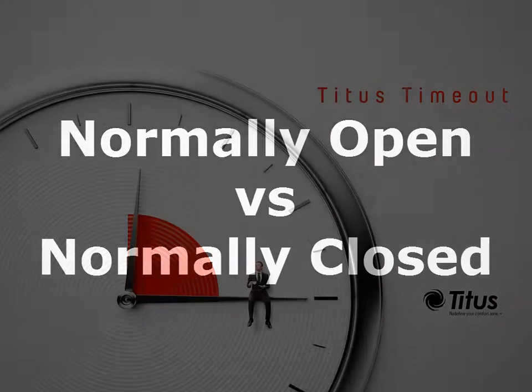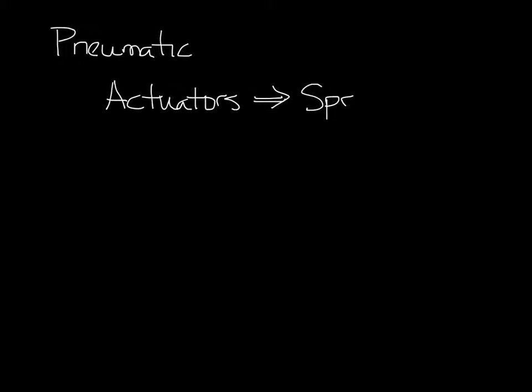I'm Jenny Abney-Civy, and today we're going to discuss the difference between normally open and normally closed VAV boxes. This terminology goes back to the days of pneumatic controls. Pneumatic actuators have an internal spring that is controlled by air pressure. When the air pressure is less than the spring tension, the actuator will retract.